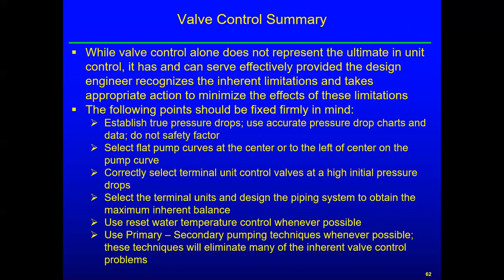So it may well be that reverse return is going to be better. It just depends on your system. Use reset water temperature control wherever possible. That would probably be part of your boiler selection, potentially your chiller selection as well. You get an automatic reset on that. And use primary-secondary pumping techniques wherever possible. The next big module in this course will be primary-secondary, so I will reserve comments until we get there.